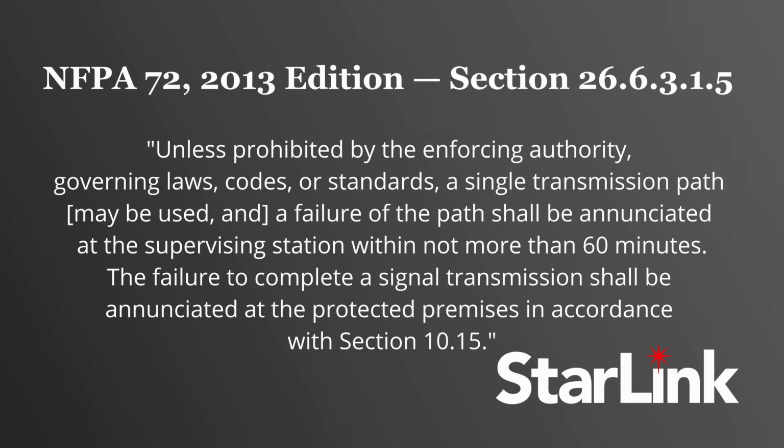Starting with NFPA 72 2013 edition, section 26.6.3.1.5 states the following. Unless prohibited by the enforcing authority, governing laws, codes, or standards, a single transmission path may be used, and a failure of the path shall be annunciated at the supervising station within not more than 60 minutes.